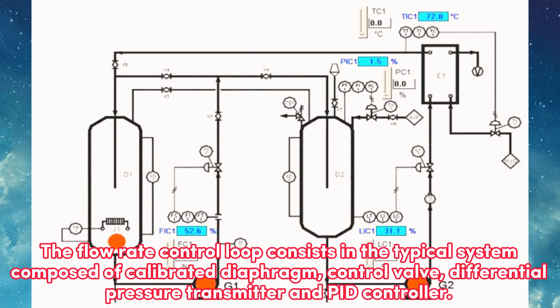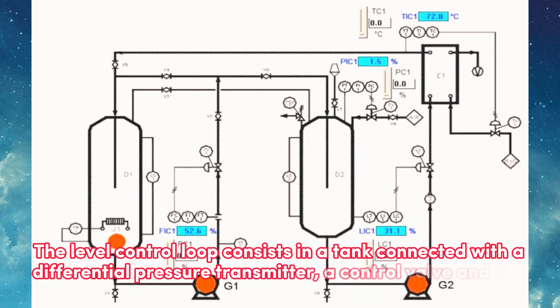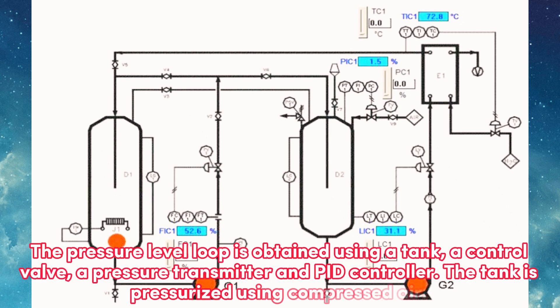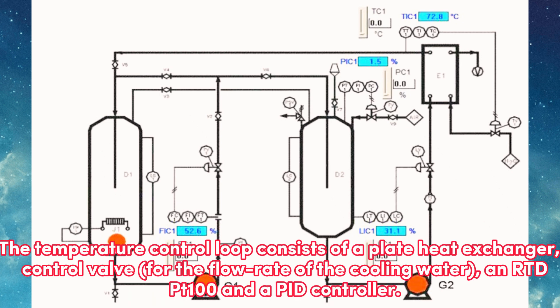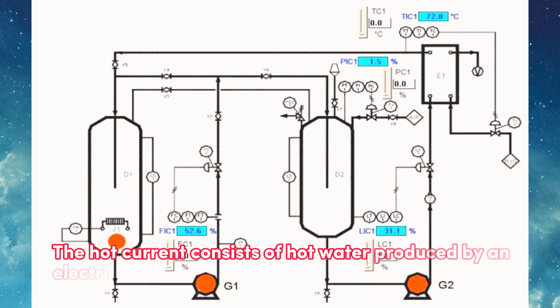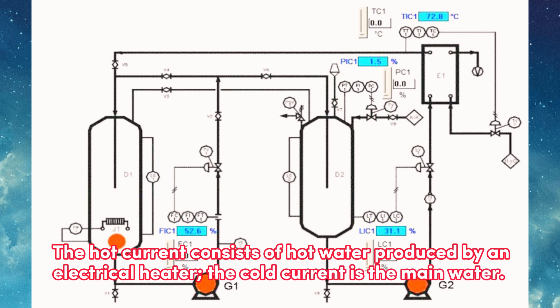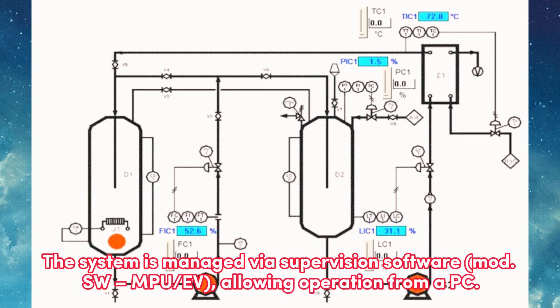The flow rate control loop consists of a calibrated diaphragm, control valve, differential pressure transmitter, and PID controller. The level control loop consists of a tank connected with a differential pressure transmitter, a control valve, and PID controller. The pressure control loop uses a tank, a control valve, a pressure transmitter, and a PID controller — the tank is pressurized using compressed air. The temperature control loop consists of a plate heat exchanger, a control valve for the flow rate of cooling water, an RTD PT100, and a PID controller. The hot current consists of hot water produced by an electrical heater; the cold current is the main water. The system is managed via supervision software mod. SW – MPU/EV, allowing operation from a PC.